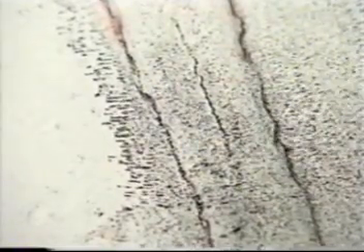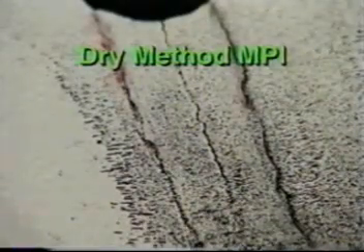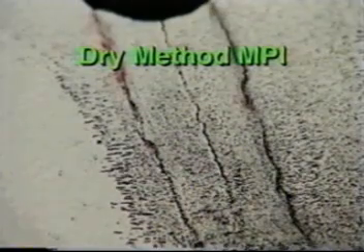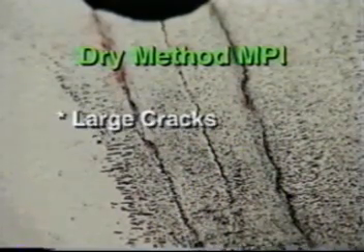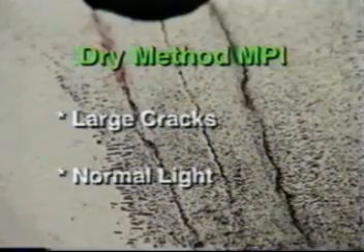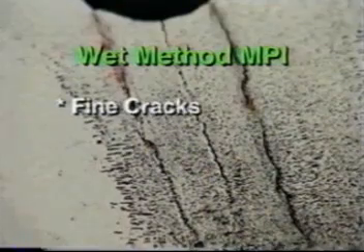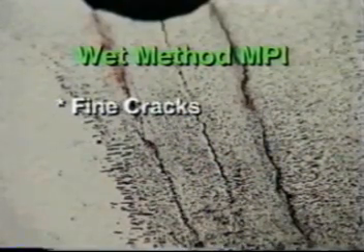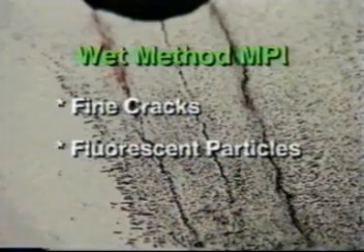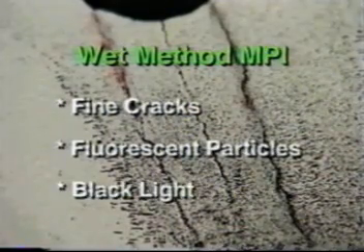When powder is applied, visible indications appear immediately because the magnetic particles are strongly attracted to any spot where a crack has created a leak in the magnetic field. The dry method magnetic particle inspection is fine for locating larger surface cracks in normal light. But if you need to find very fine surface flaws, you need the magnetic particle wet method using fluorescent particles in a black light.